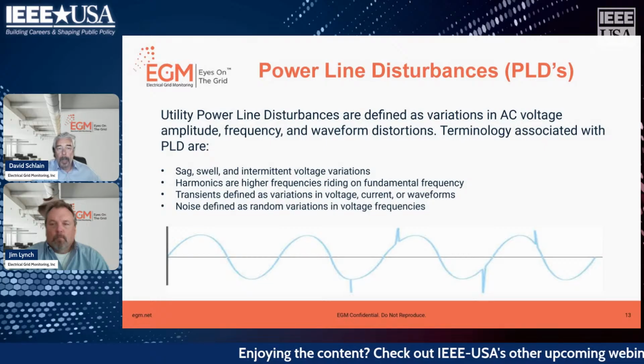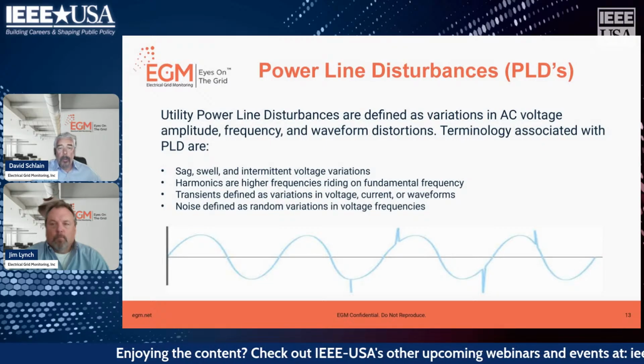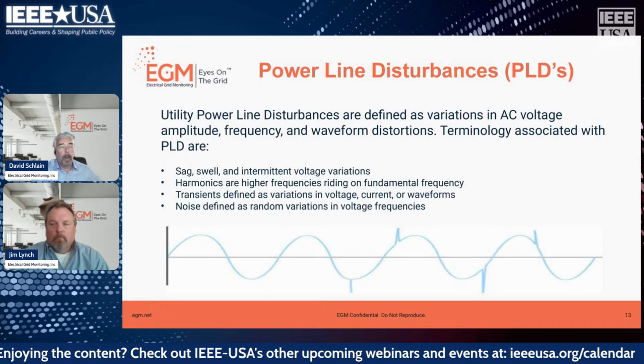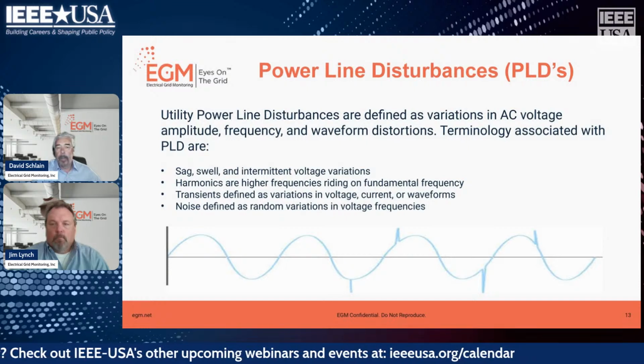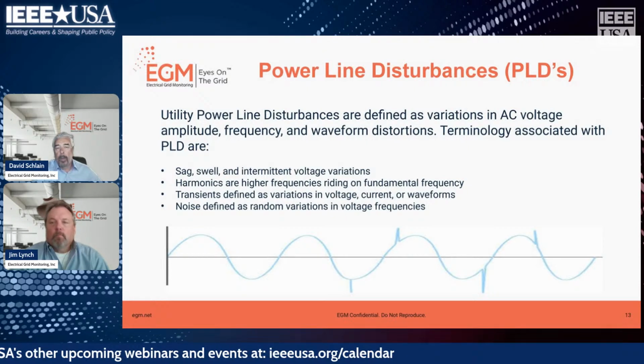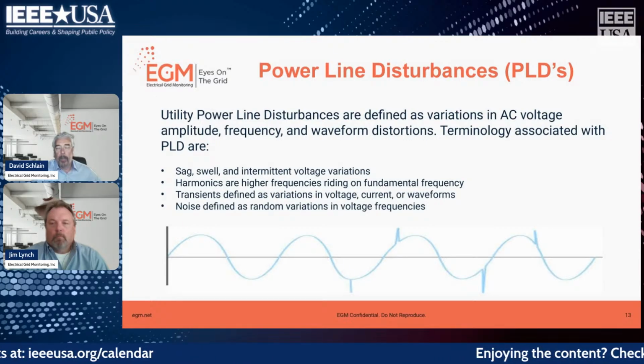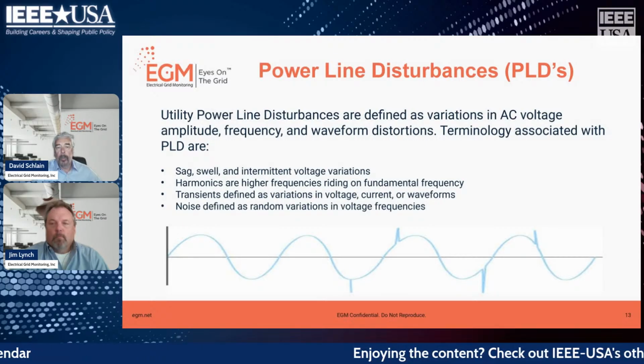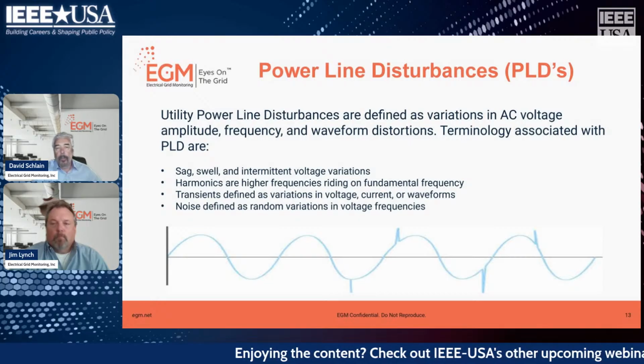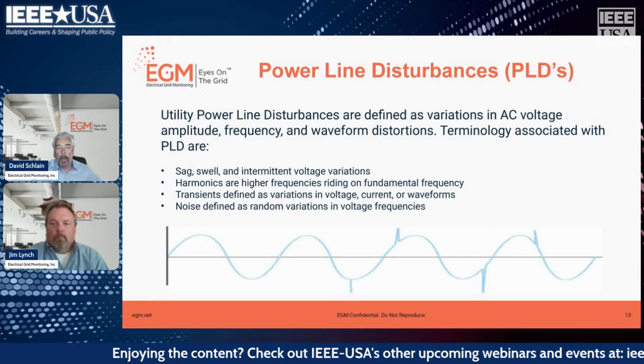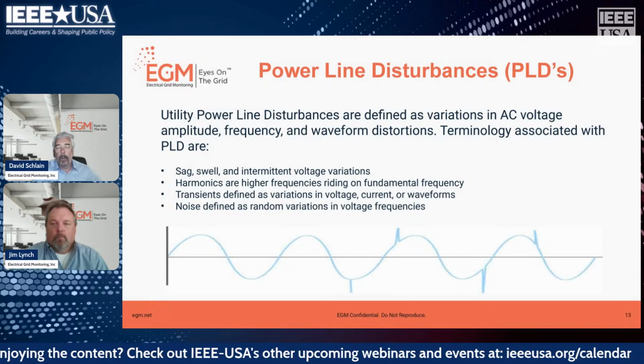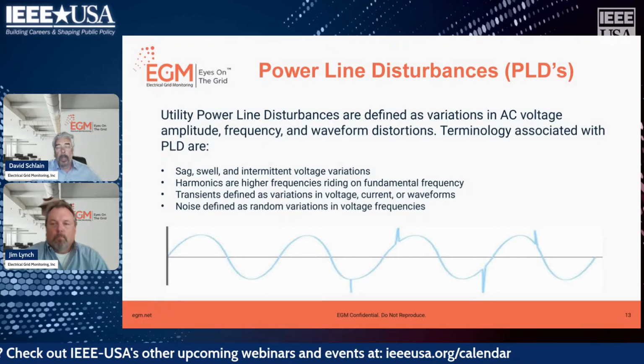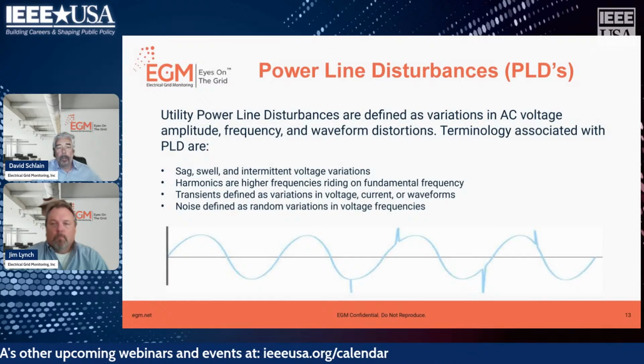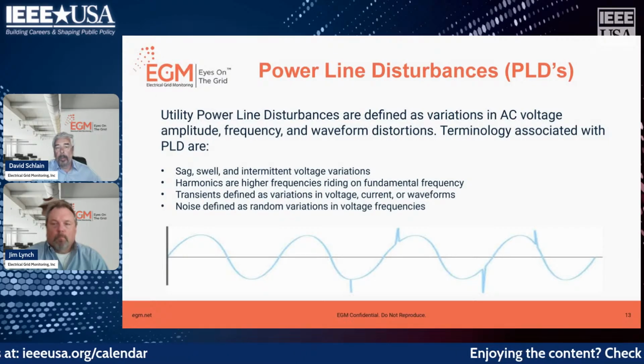So the solution platform measures the harmonics on a line. Harmonics can be caused from many sources. One of the most common is inverters, right? You have a PV field and you want to take that DC voltage and convert it to AC. Those inverters cause quite a bit of harmonic frequencies onto your existing power lines. These can be problematic for utilities because they need to understand the effects on power quality.